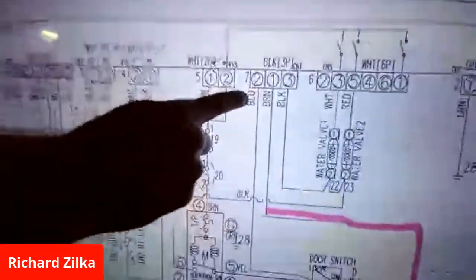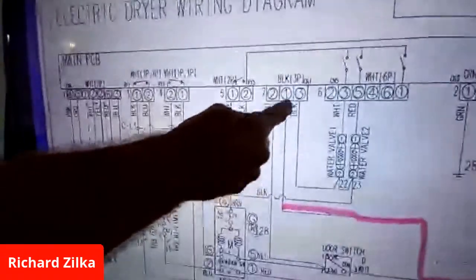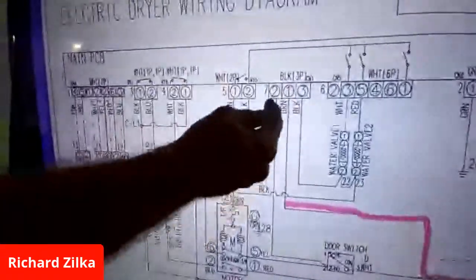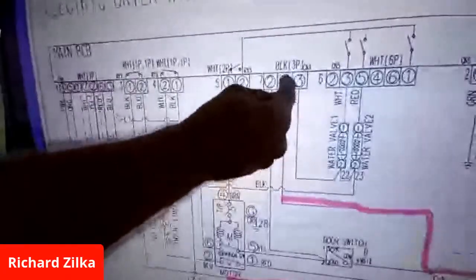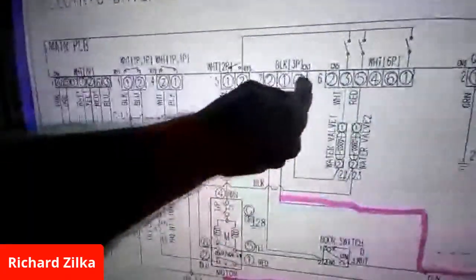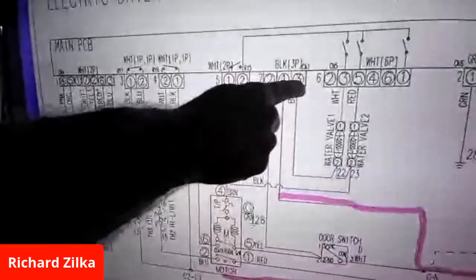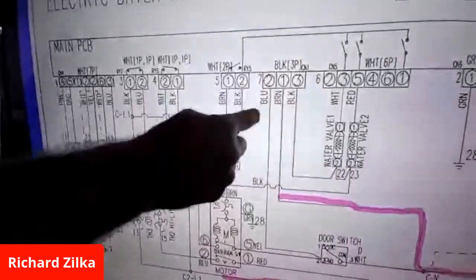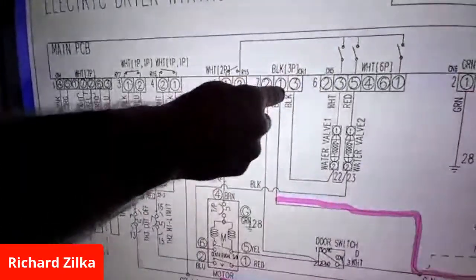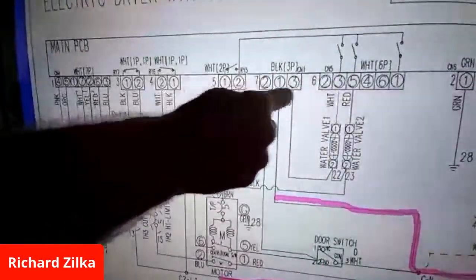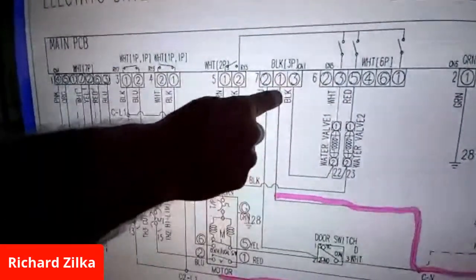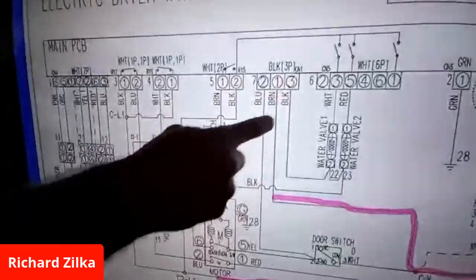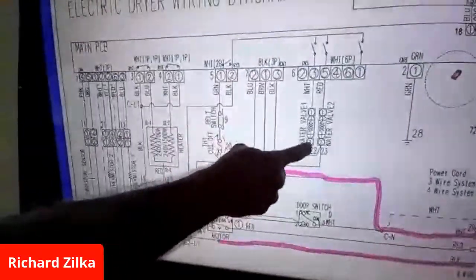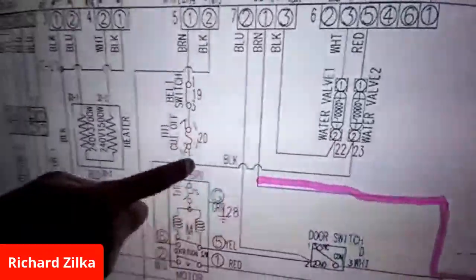Black and brown here, 1 and 3. Notice how the brown was on the outside and the blue was in the middle physically, but look at the number system—number 1 was brown, number 2 was blue, black is 3. So the numbering system here is different from how we'd normally see it: brown is on the outside because it's number 1, blue in the middle is number 2, and black is number 3. So we check brown and black. If we follow them back, black here jumps off the water valve and comes around here.